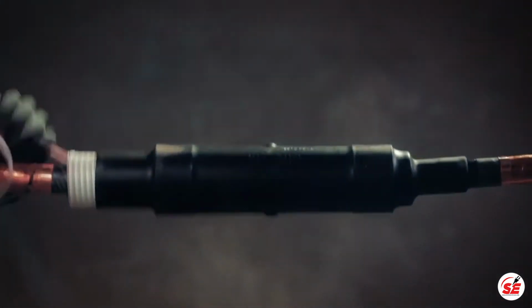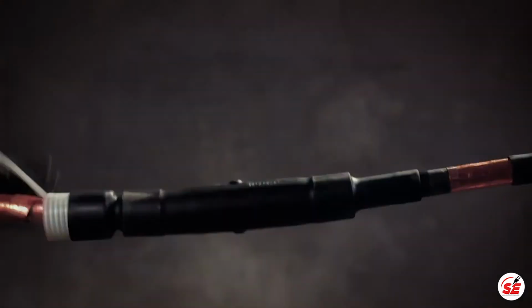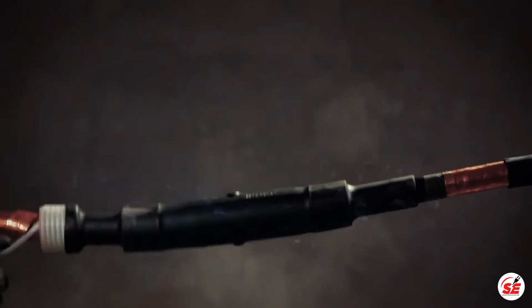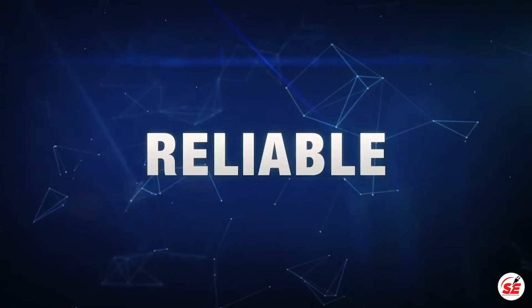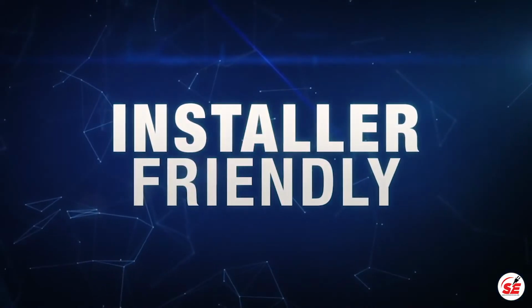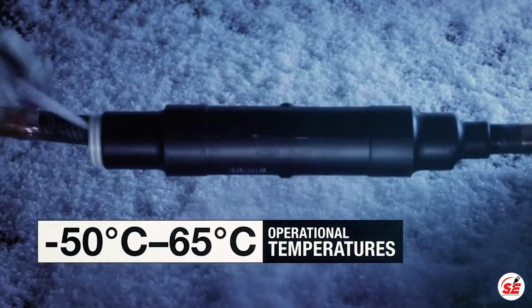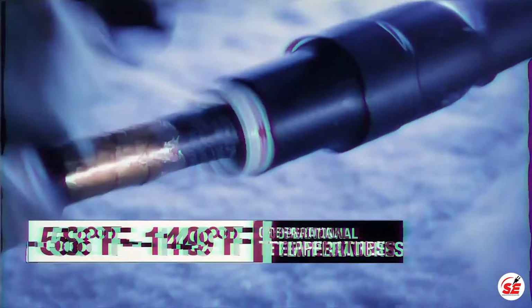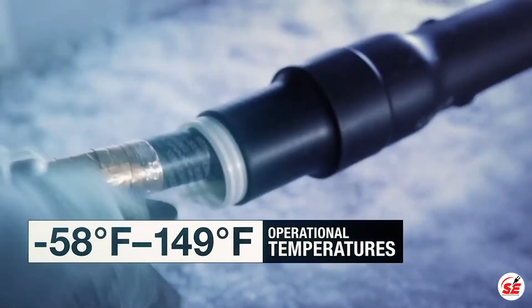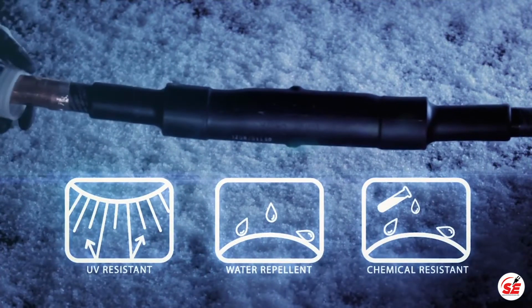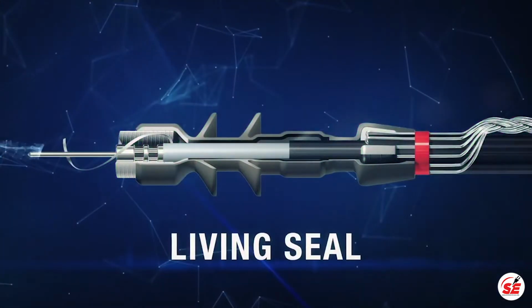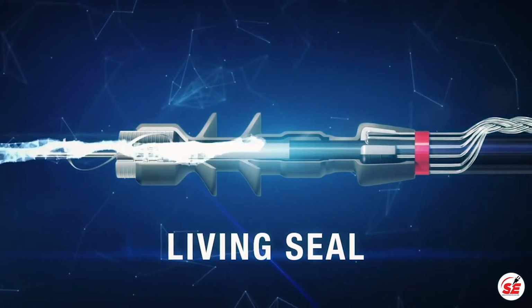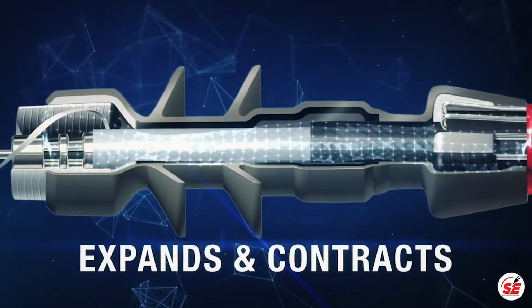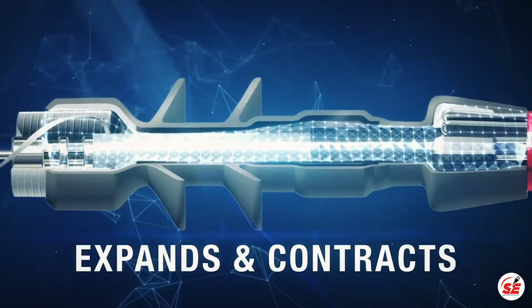3M brand cold shrink medium voltage cable accessories feature a rubber tube that shrinks around your cable once the removable core is unwound. 3M cold shrink products offer an alternative to heat shrink with a reliable and more installer-friendly design. Cold shrink technology provides a more consistent installation independent of physical location or environment, without the use of a torch or hot work permit. Plus, 3M brand cold shrink provides an environmental seal that expands and contracts with the cable, providing a living seal.